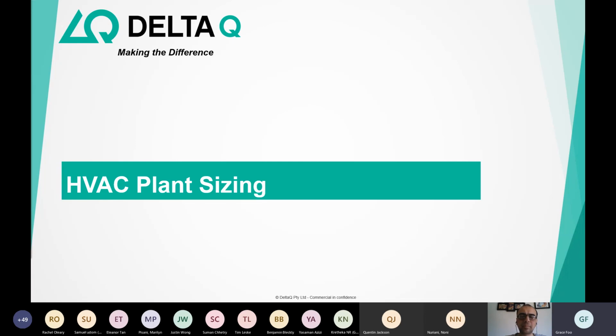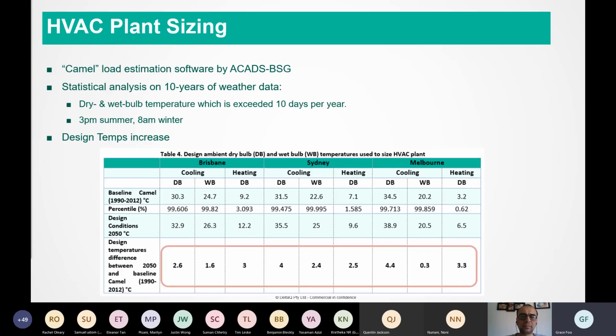So coming back to the presentation, we also looked at the impacts of using a future climate file on HVAC plant sizing. As I mentioned before, the software Camel was used, and I would say for those of you that are not quite aware, the design day, or your design temperatures, drive plant sizing. Sometimes you see them in your ASHRAE handbook or the DA09, which is the heat load estimation manual, if I'm not mistaken, with the title.